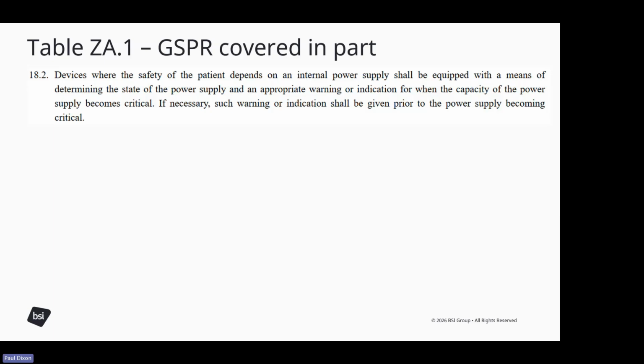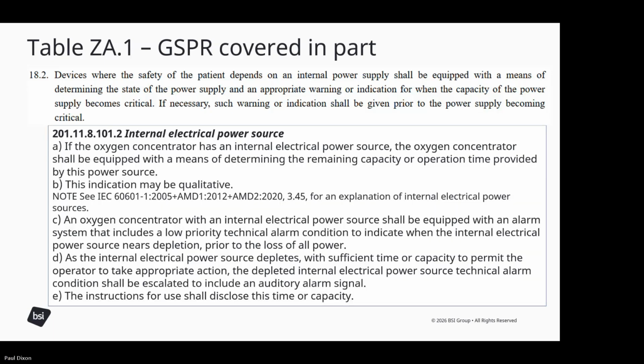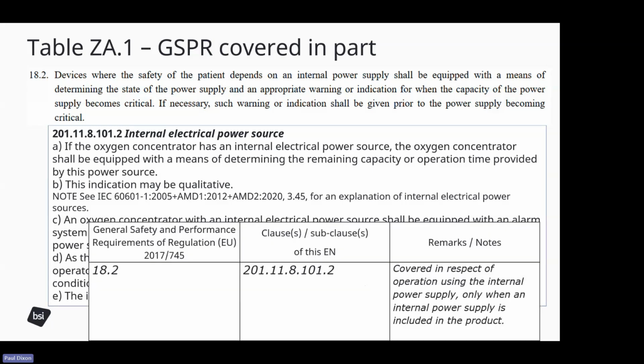Another example, internal power supply. In this case, this is the same oxygen concentrator standard. We have a conditional requirement. If the oxygen concentrator has an internal electrical power source, then it shall meet these requirements. In this case, the coverage was accepted. 18.2 is regarded as being covered by this clause, but only when the internal power supply is included in the product. So if you have an oxygen concentrator that has an internal power supply, you can use this clause to show coverage of 18.2. If your product does not, you cannot.